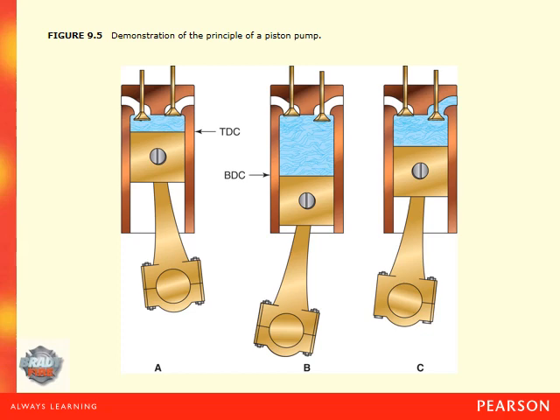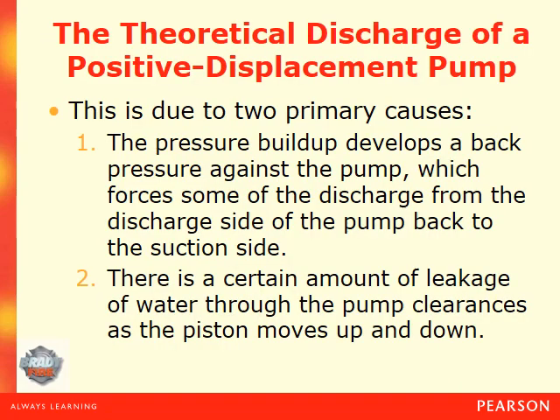Here is a demonstration of the principle of the piston pump. The theoretical discharge is never achieved due to two primary causes: first, pressure buildup develops back pressure against the pump, which forces some discharge from the discharge side back to the suction side. Second, there is also a certain amount of leakage of water through the pump clearance as the piston moves up and down.